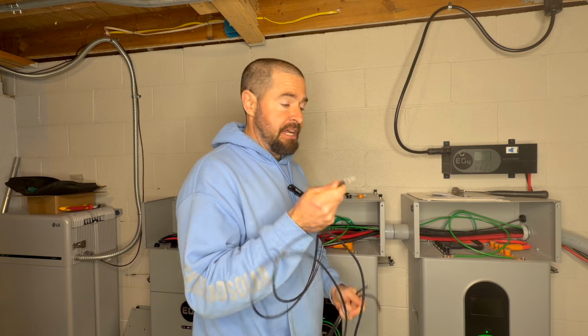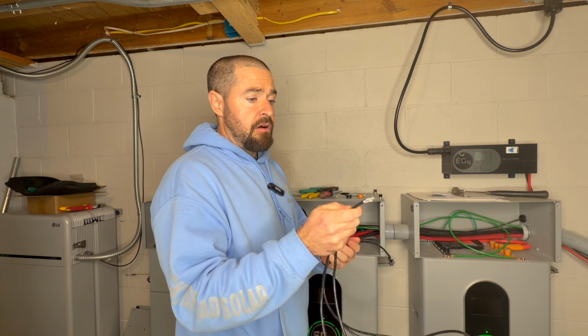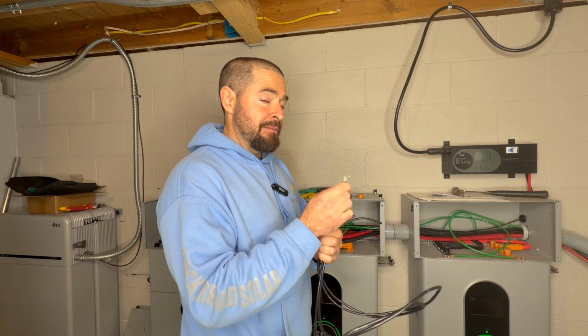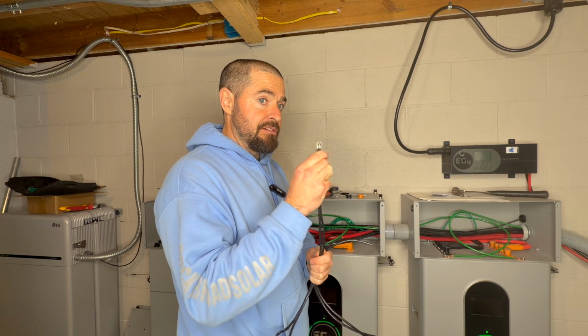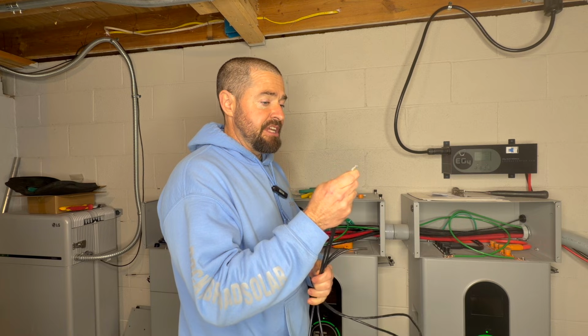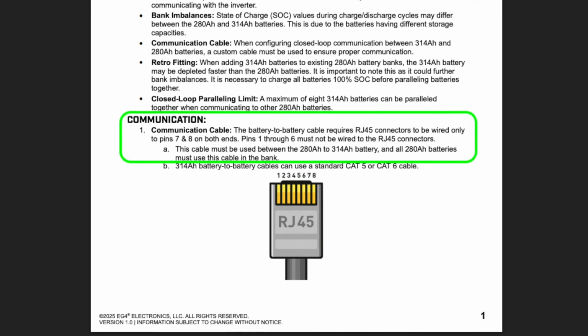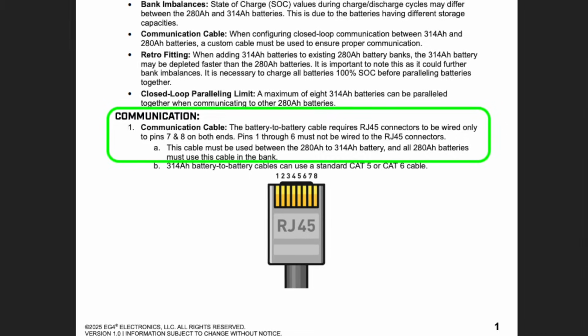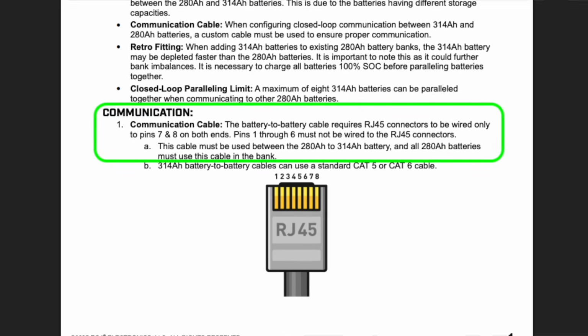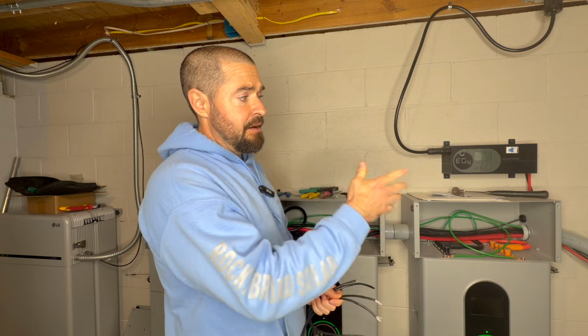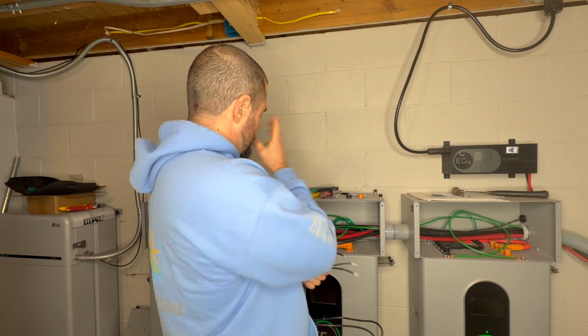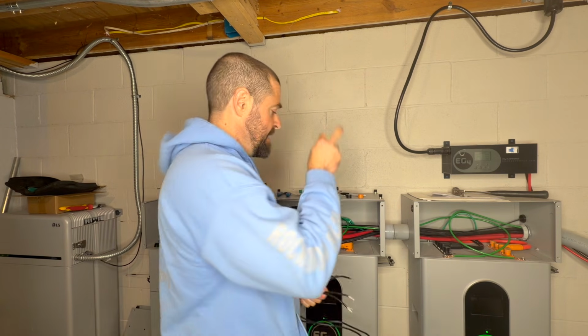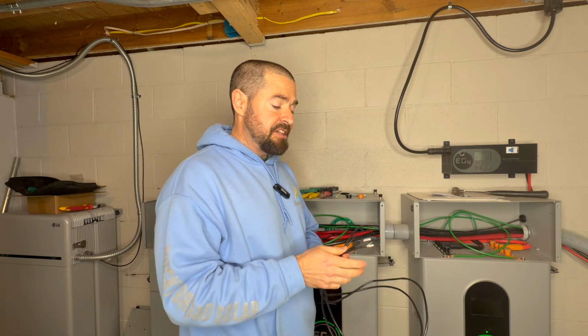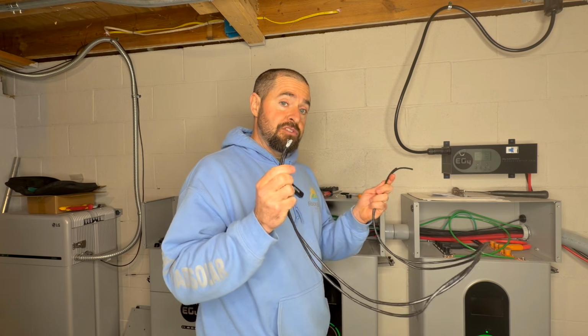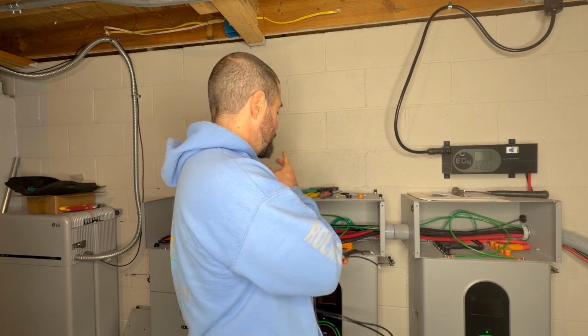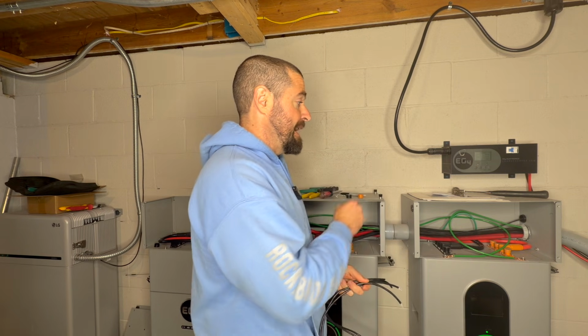They're not your standard Cat 5 RS485 cable. They only utilize 2 out of the 8 wires, and the manual specifically says only pins 7 and 8 should be used between the 314 and the 280, and between all the 280s thereafter. In my case, I have one 314 amp hour battery and 2 280 amp hour batteries, so I'll need to crimp 2 special cables to connect the 314 to the 280 and the 280 to the 280.